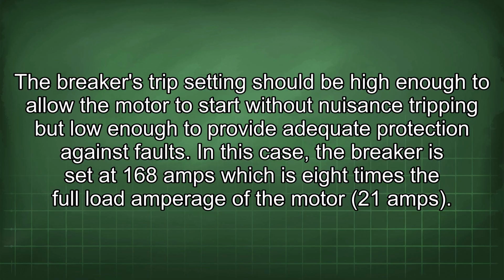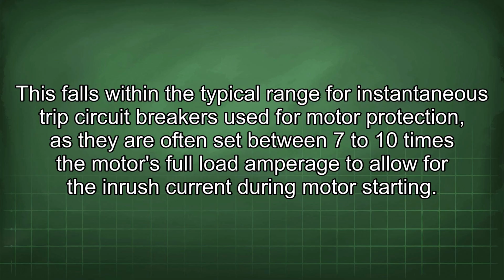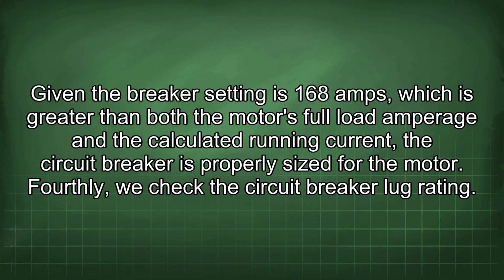In this case, the breaker is set at 168 amps, which is 8 times the full load amperage of the motor, 21 amps. This falls within the typical range for instantaneous trip circuit breakers used for motor protection, as they are often set between 7 to 10 times the motor's full load amperage to allow for the inrush current during motor starting. Given the breaker setting is 168 amps, which is greater than both the motor's full load amperage and the calculated running current, the circuit breaker is properly sized for the motor.